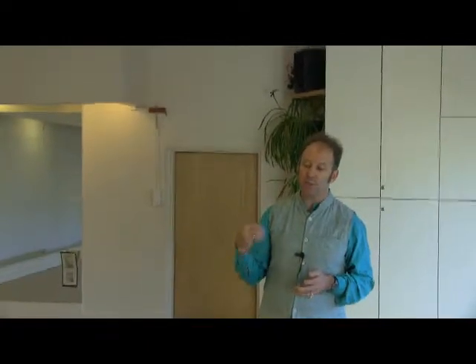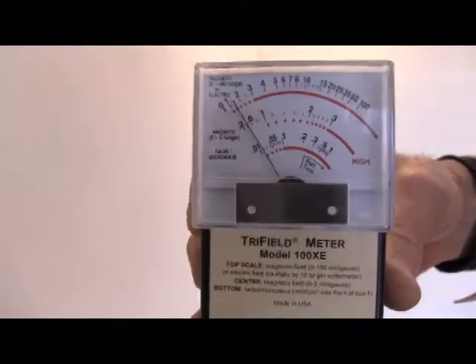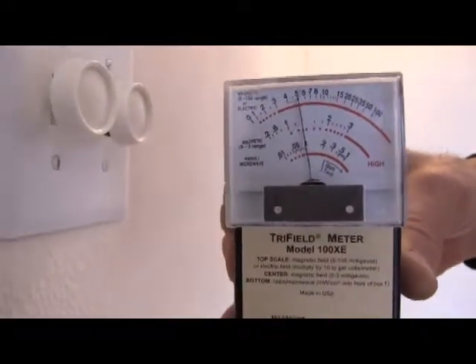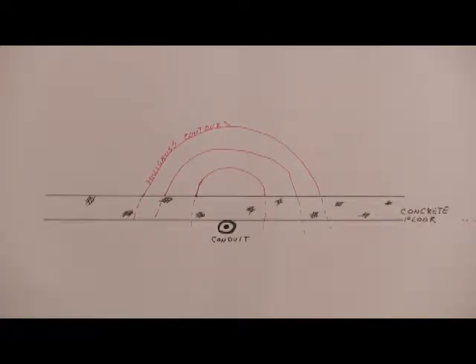So in addition to moving the ballasts into the basement, we also have a little story about electromagnetic radiation that we discovered in this room. Peter, you want to share what you found? Sure. At the beginning of the job, I took a gauss meter and walked around the building to see what the background radiation was. And in this room, I found an extremely low-frequency magnetic field coming up into the room. When I went back and forth in the room, it was a long linear feature, and that's where we discovered the subpanel wire that was buried in the slab.